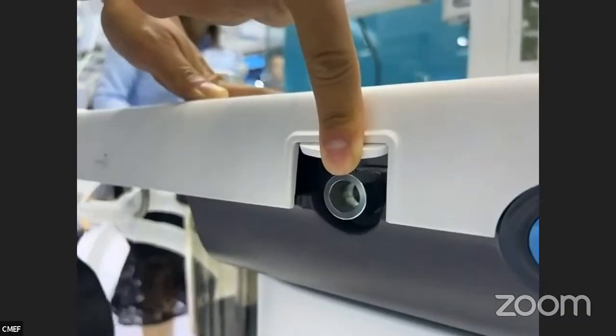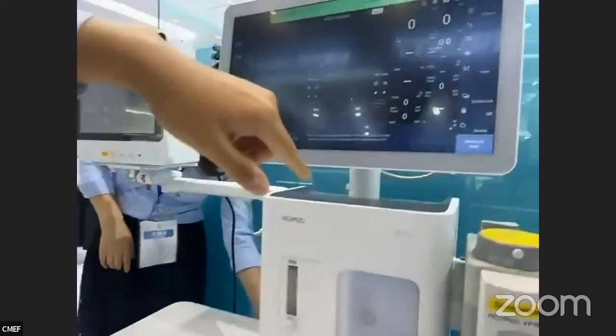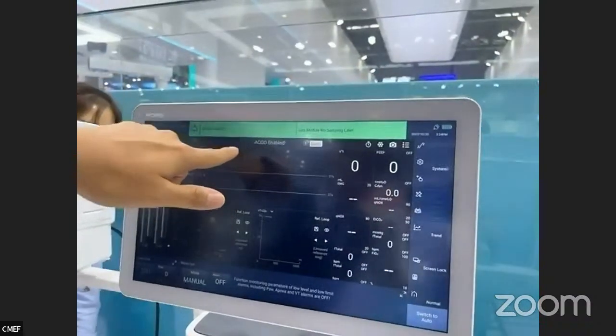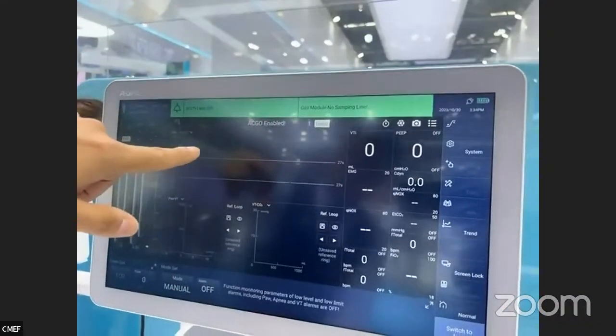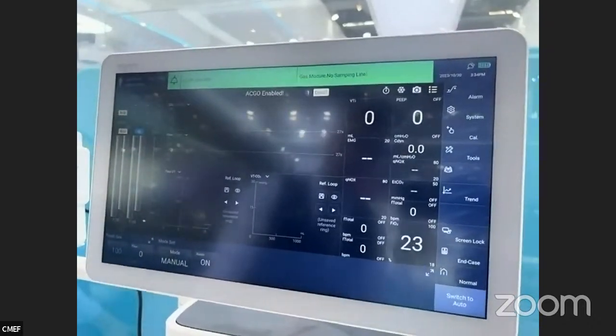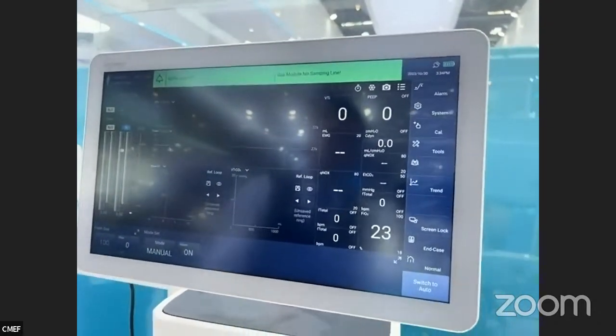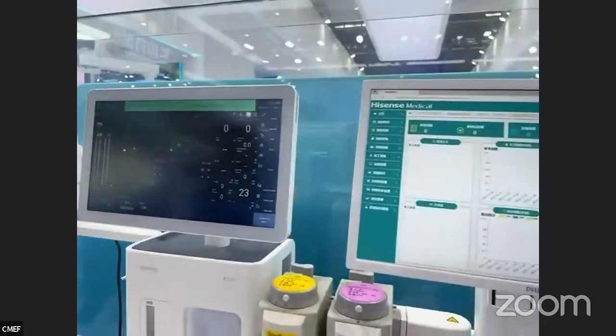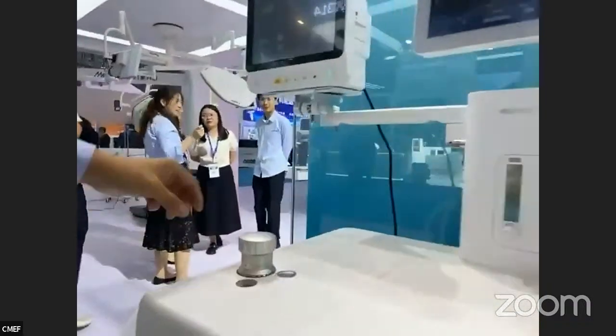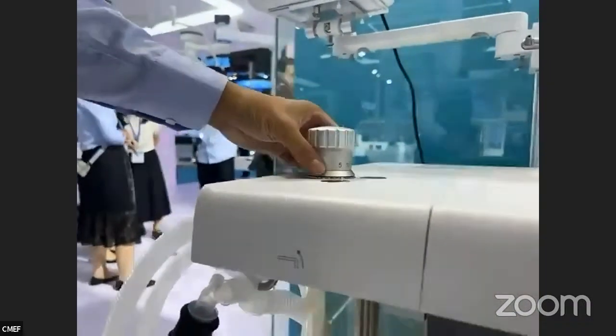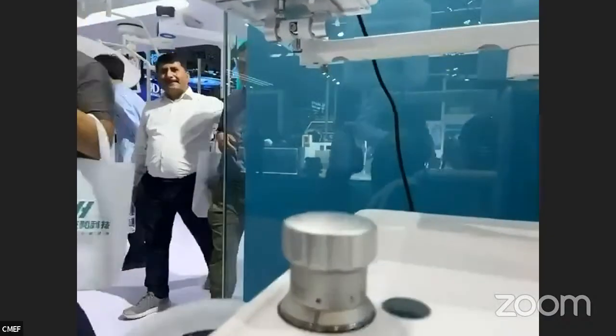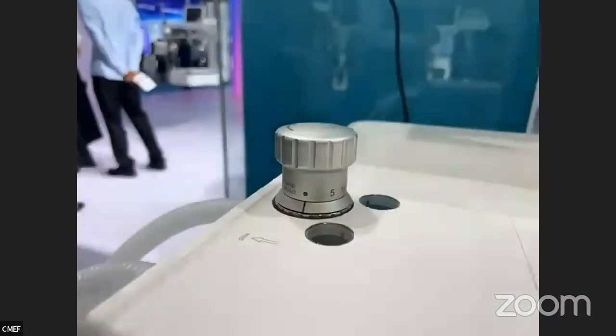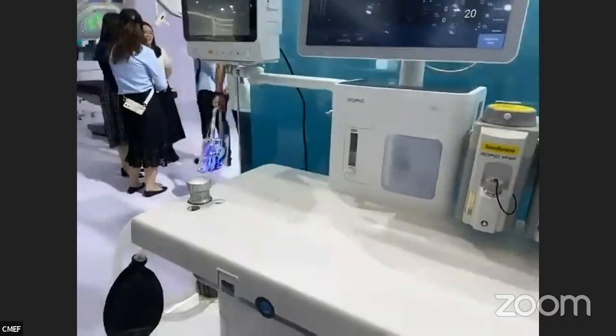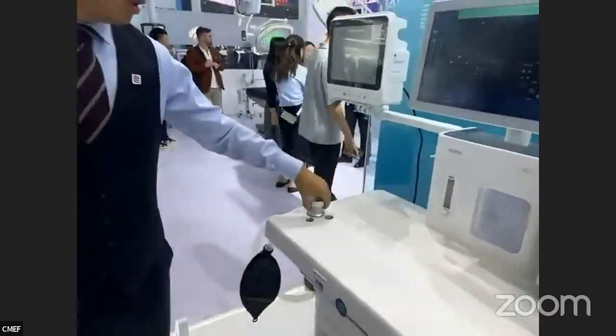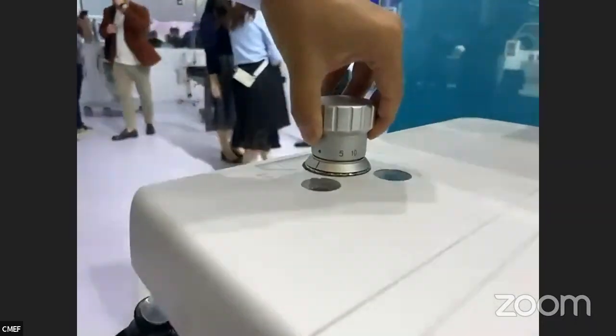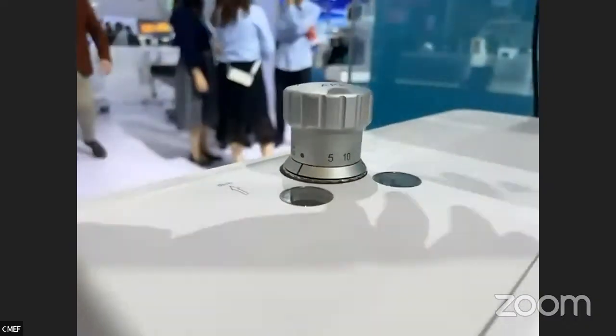As you can see, the moment when I lift this one, on the screen it's going to display ACGO enabled. And if I remove my fingers, it's closed. Then here on the breathing circuits, we have this fast release function APL valve. Whenever the anesthetist discovers an abnormally high pressure in the breathing system, in the airway, what he has to do is just lift up this APL valve to do a quick release of airway pressure.